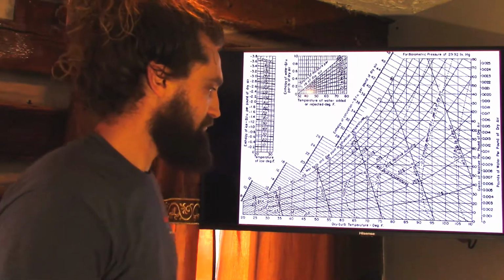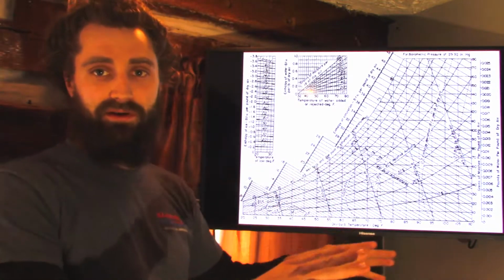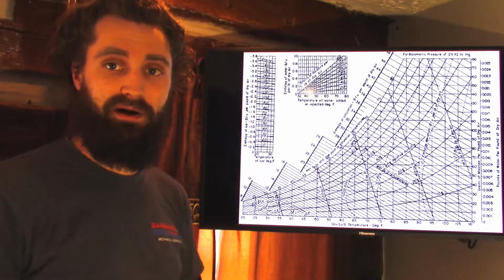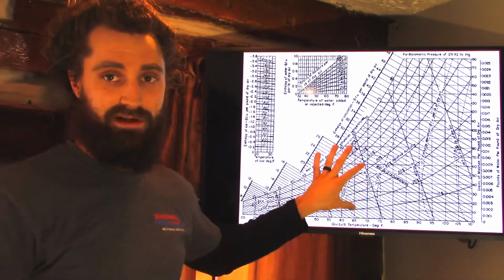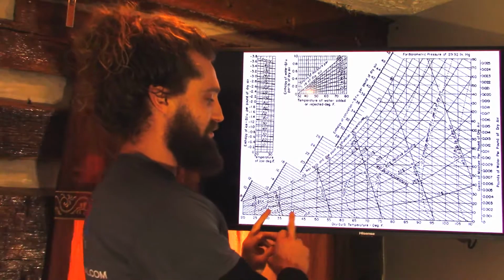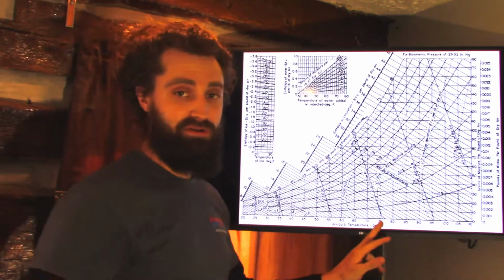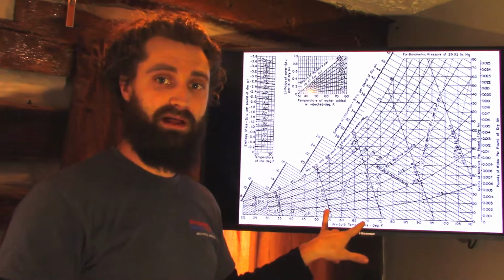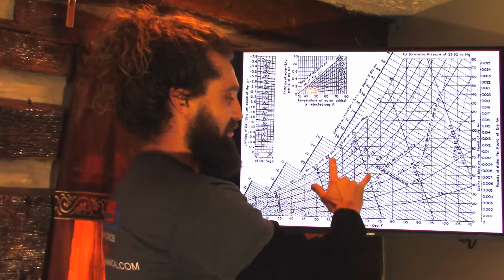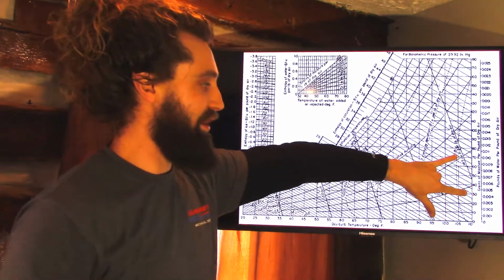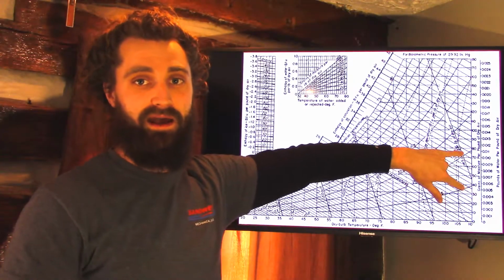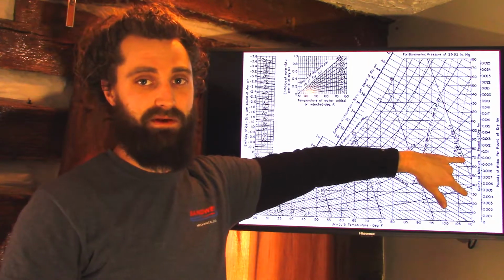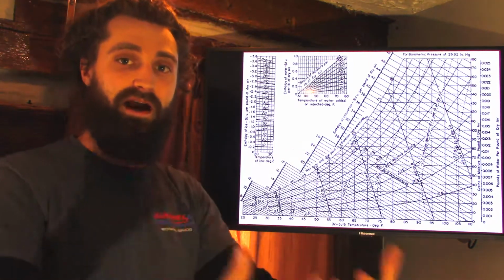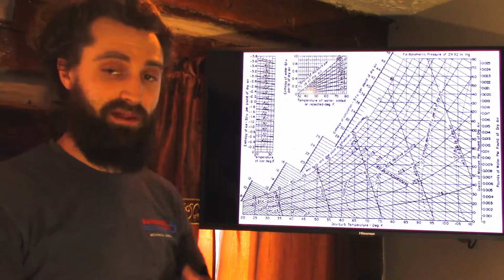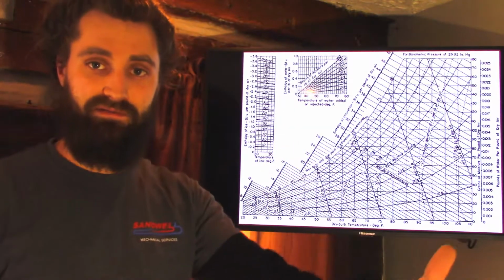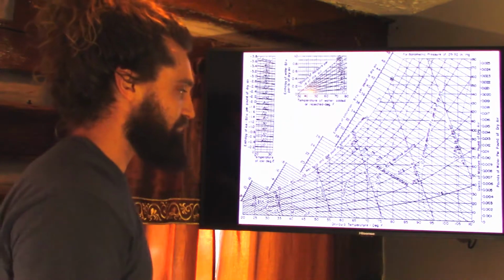I have another video that goes into more depth on this, but basically your service technician should pull this chart out, look at the temperature of the house at the return and the supply, and go across the chart to see how many grains of moisture we need to add into the airstream to reach our desired humidity level, whether that's 30%, 40%, or 50%.